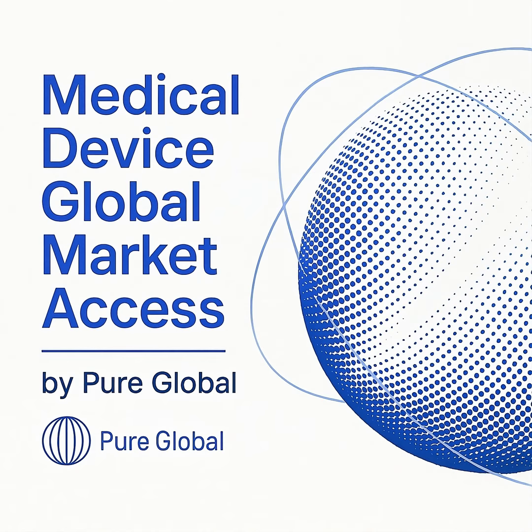The impact on IVD manufacturers is significant. New labeling, including EN ISO 15223-1 symbols and registration rules, enhance traceability. Manufacturers, EU ARs, and importers must register in EUDAMED. Distributors also have IVDR obligations despite not registering. IVDs face border checks for labeling and documentation, like safety data sheets per REACH for reagents. The EUDAMED database aids authorities in systematic searches, with surveillance a European Commission priority.